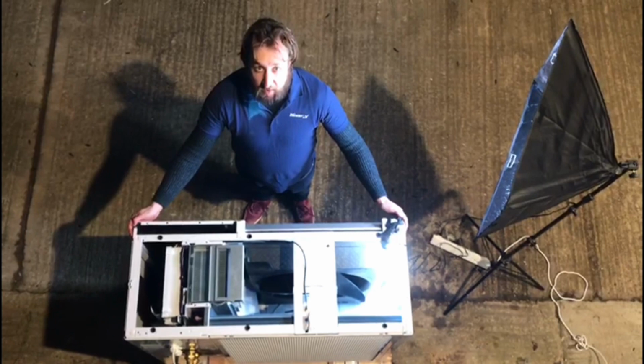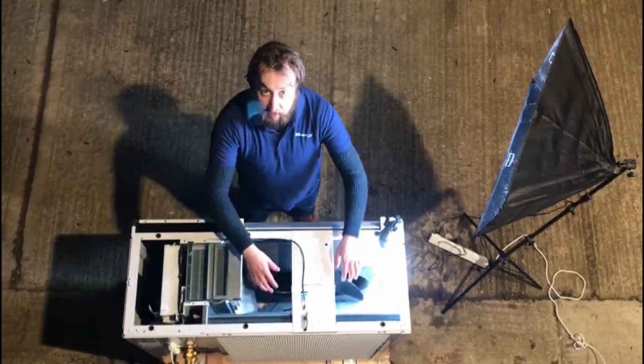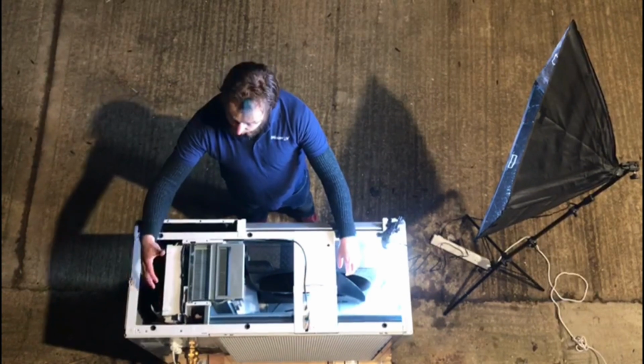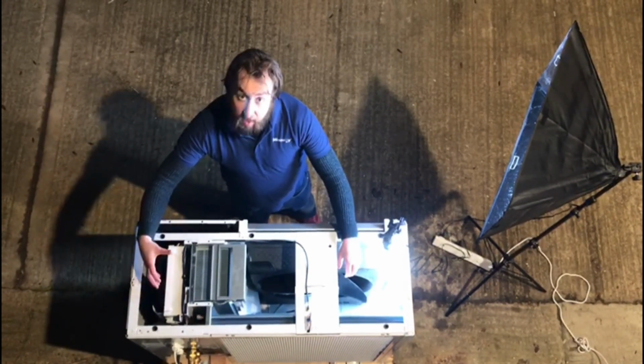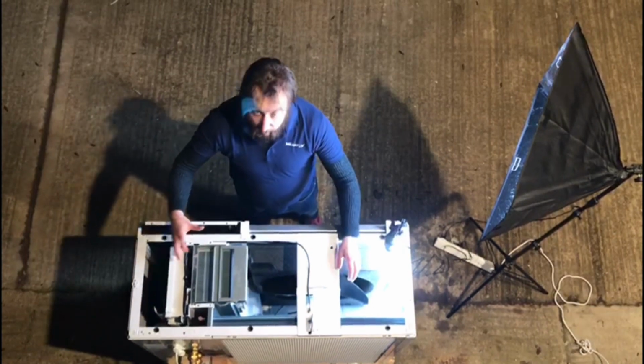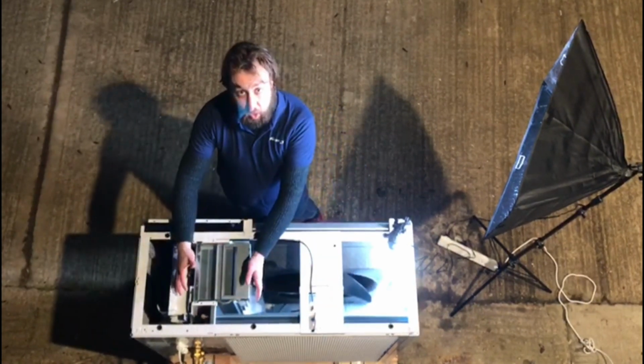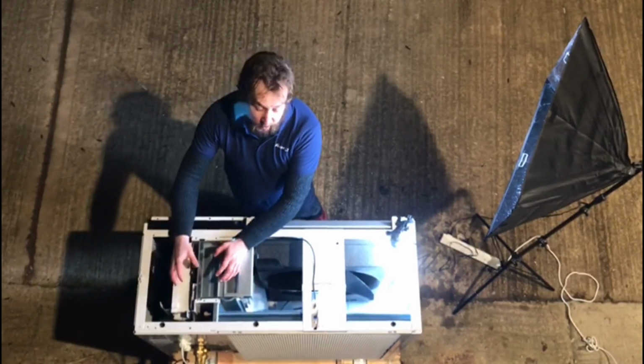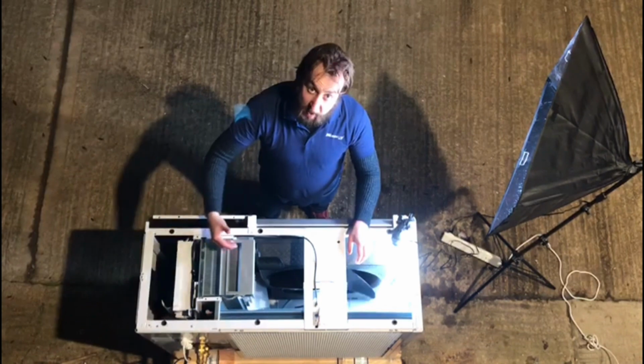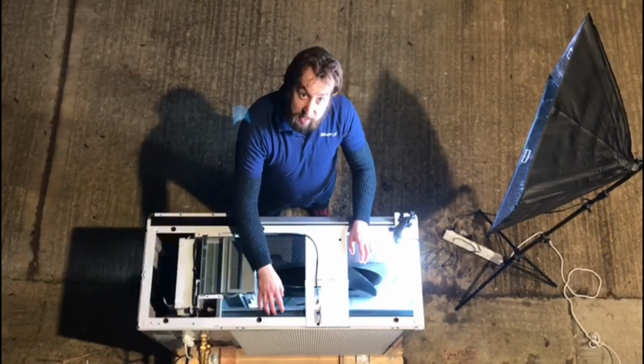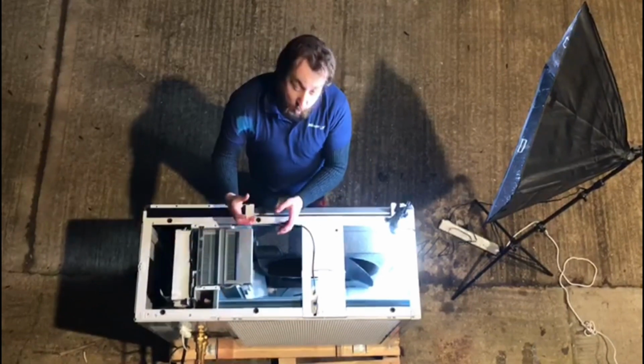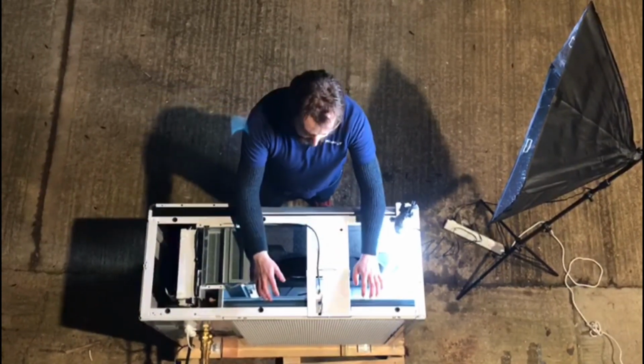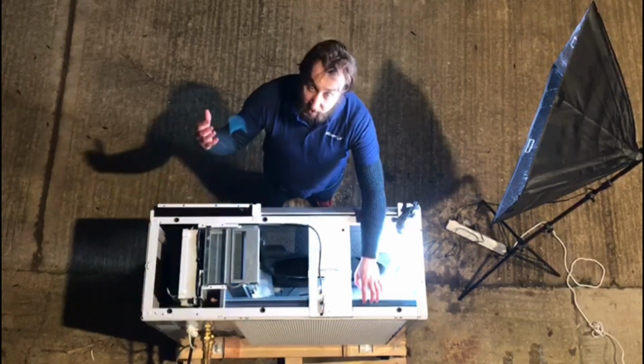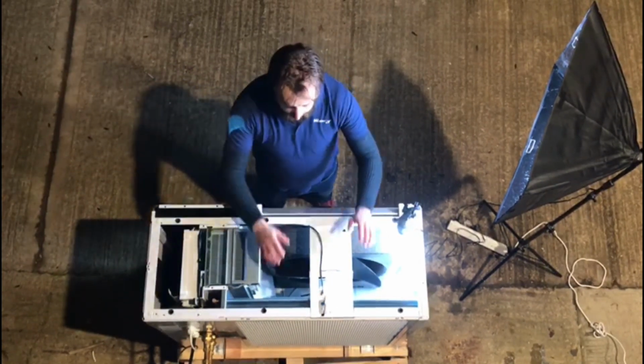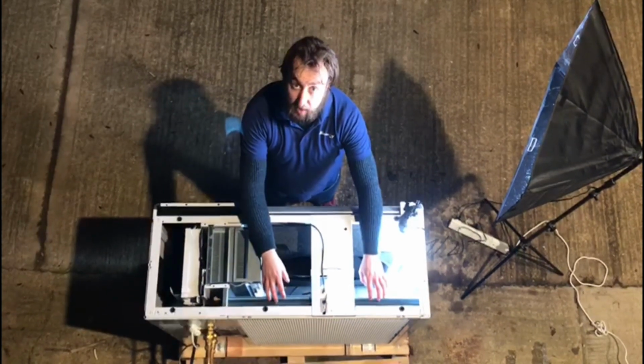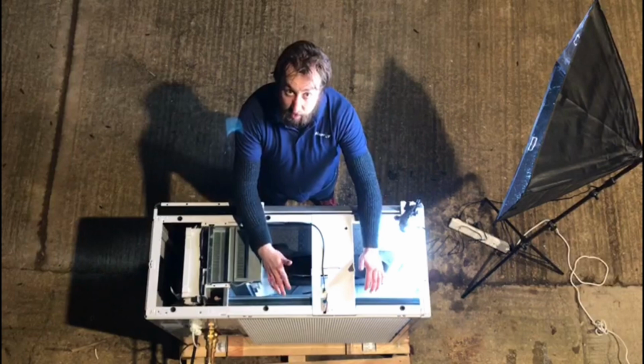So we've taken the lid off this heat pump and you can see the radiator, the fan, this compartment here within which we have the compressor, the condenser, the plate heat exchanger and the expansion valve through which the refrigerant flows. We've also got the electronics which modulates the speed of the compressor motor. So the refrigerant comes out of the expansion valve over here into this radiator, and as it depressurizes it goes from a liquid into a gas state, gets very cold, and it's this drop in temperature that allows us to transfer heat from the air that's flowing through the fan through the radiator. It gets much colder than the surrounding air, allowing us to get heat back into the refrigerant.